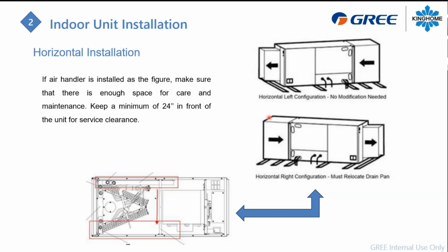If it's a horizontal display like this, if you lay it down on the left, the drain pan is already on the left side of the unit, so you don't have to change the configuration. But if you flip it on the right side and you have another horizontal right configuration, at this point you will have to relocate the drain pan. So you will have to remove that coil, change the secondary pan here to flip it on the other side, and then you're good to go.